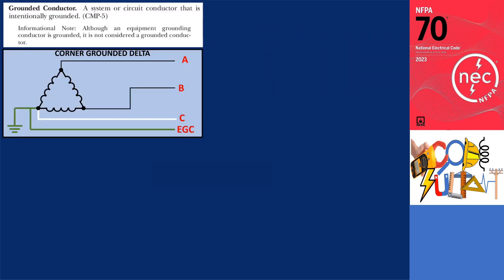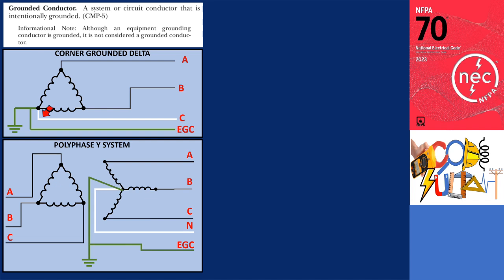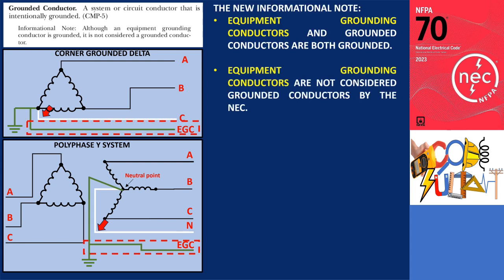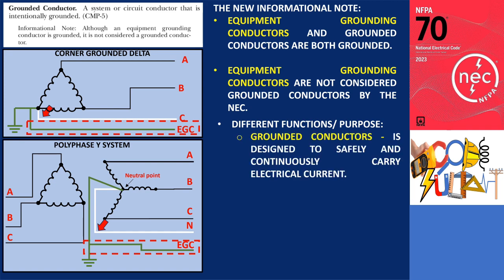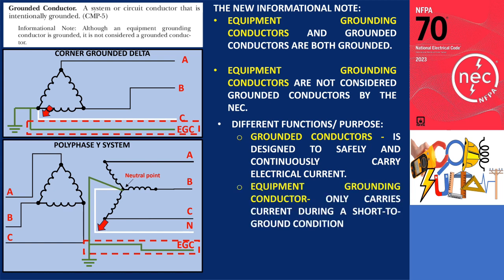The grounded conductor refers to a system or circuit conductor intentionally connected to the ground. In the provided illustration, a corner grounded delta configuration is depicted where phase C is connected to the ground; therefore, conductor C serves as the grounded conductor. Another illustration showcases a polyphase Y system, where the neutral conductor is the conductor connected to the neutral point of a system, intended to carry current under normal conditions. Since the neutral point is intentionally connected to the ground, the grounded conductor in this illustration is the neutral conductor. However, the equipment grounding conductor is also grounded, but is not considered a grounded conductor — this distinction helps electrical practitioners differentiate grounded conductors from grounding conductors. Grounded conductors are designed to safely and continuously carry electrical current, while equipment grounding conductors only carry current during a short-to-ground fault condition.